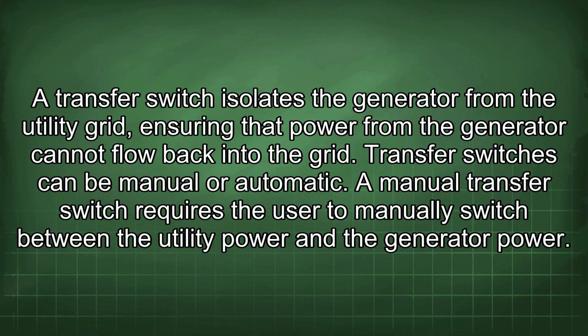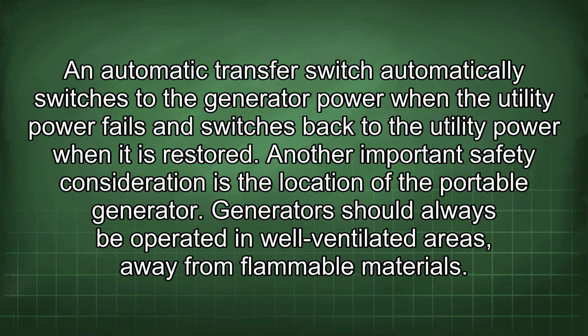A manual transfer switch requires the user to manually switch between the utility power and the generator power. An automatic transfer switch automatically switches to the generator power when the utility power fails and switches back to the utility power when it is restored. Another important safety consideration is the location of the portable generator.